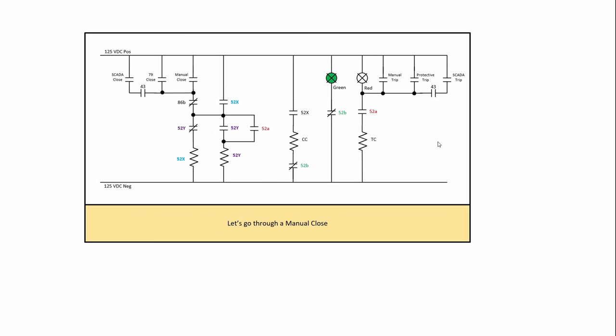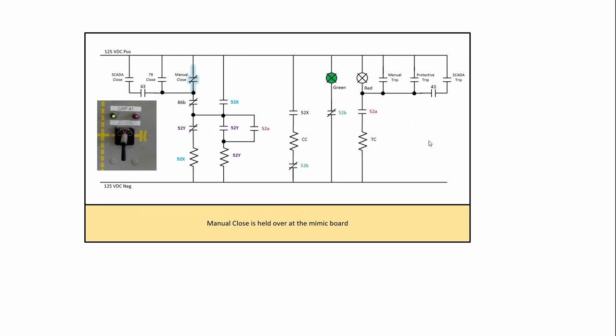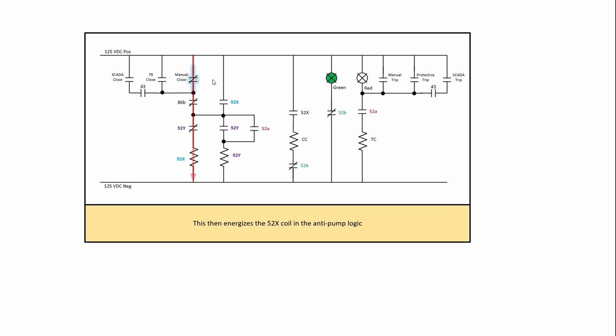So let's go through a manual close. First, we close the circuit breaker with a mimic board control. And so that creates a path here through our 86B. We don't have a lockout relay. And we pick up the 52X. Once we pick up that 52X, its 52X contacts change state, this one right here will energize the closed coil. And this one right here will lock in the 52X, seal it in.